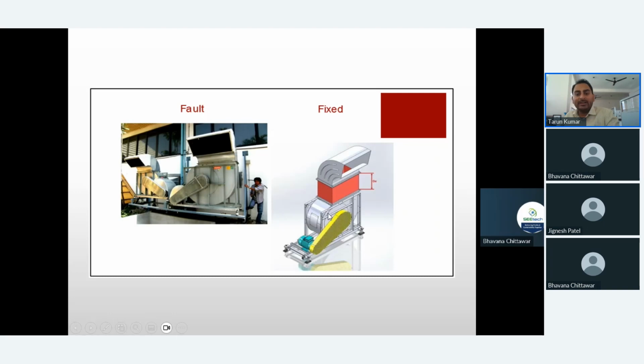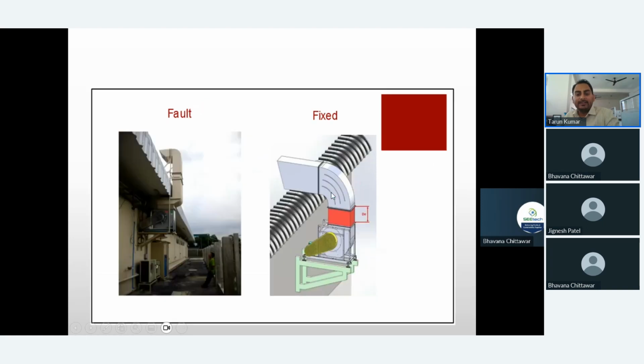Whenever you are putting in the fan, there should always be a flexible connection between the duct and fan, and the duct should be straight as well for a certain distance. You can see the photograph over here. This photograph clearly shows that direct back pressure is being generated over the fan.